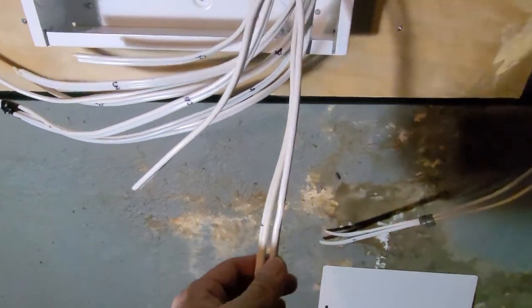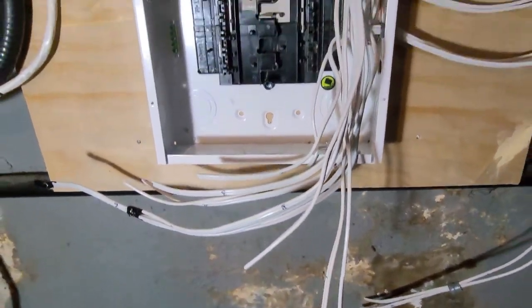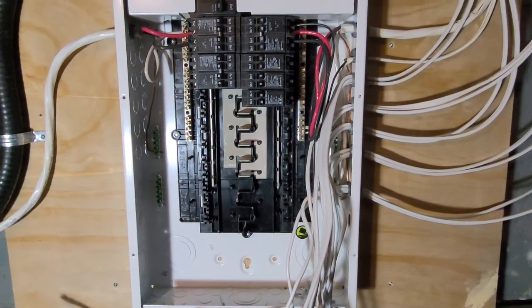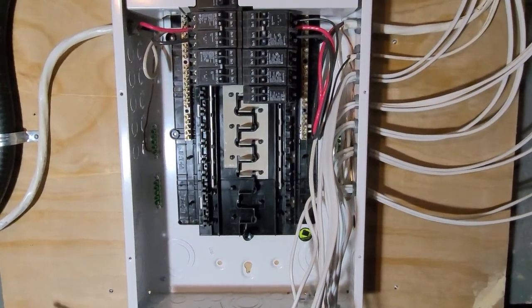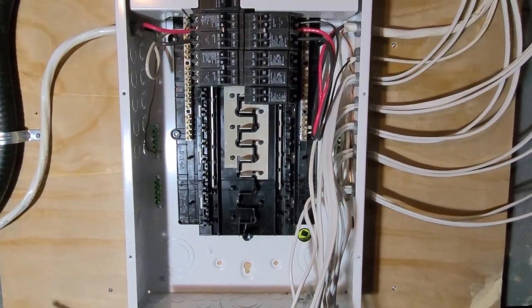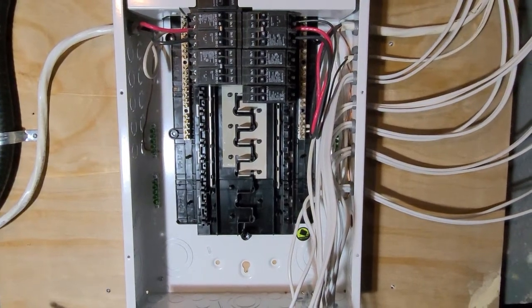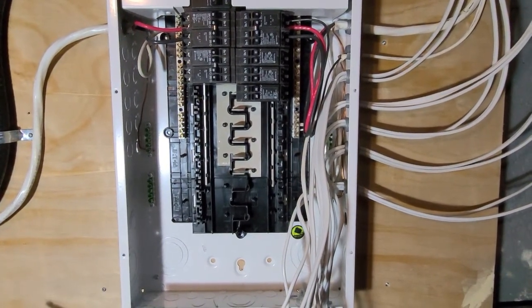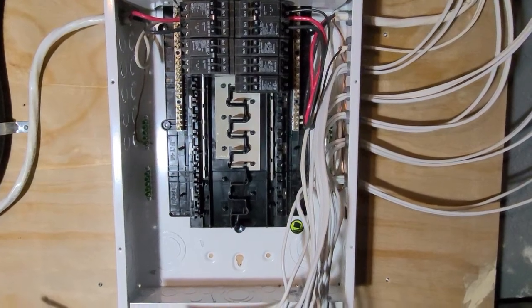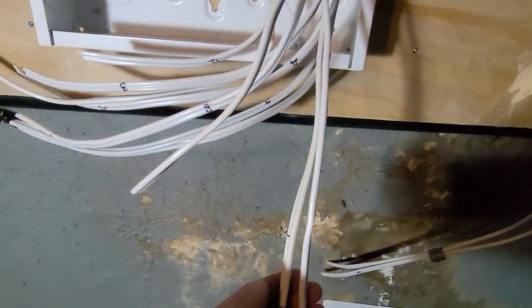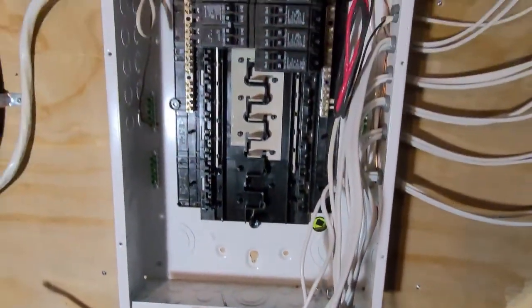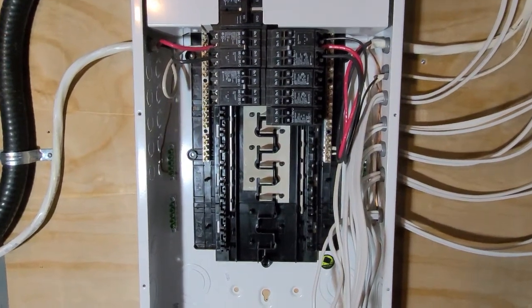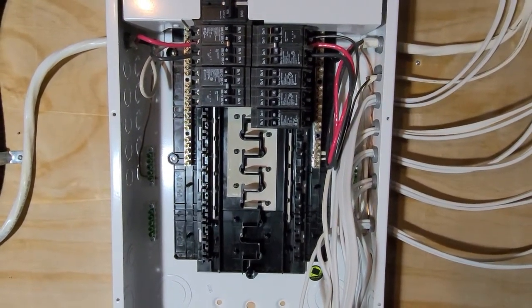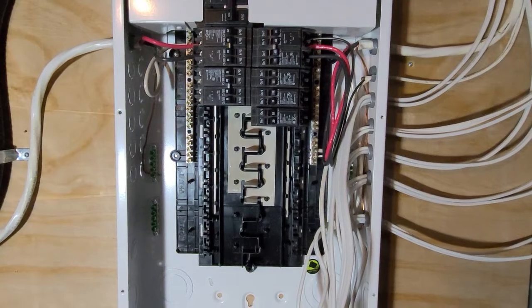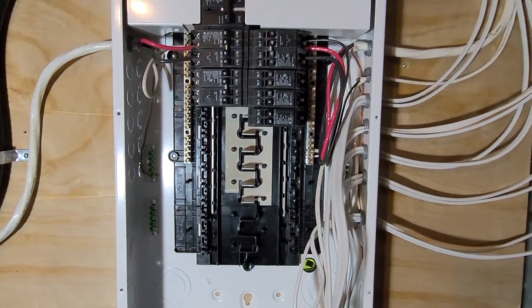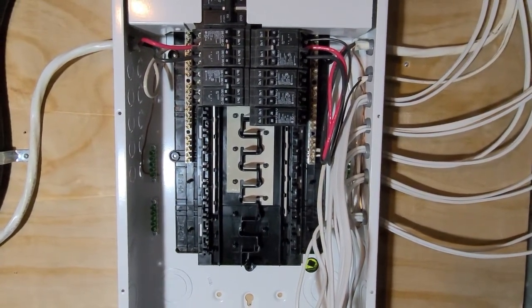And according to the new electrical code rule, certain receptacles need to be arc fault combination type. So basically, it protects you from the series arc fault and the parallel arc fault, which requires the neutral to terminate into the breaker, not just to the neutral bar in the electrical panel. I will show you guys later what the combination type arc fault breaker looks like.